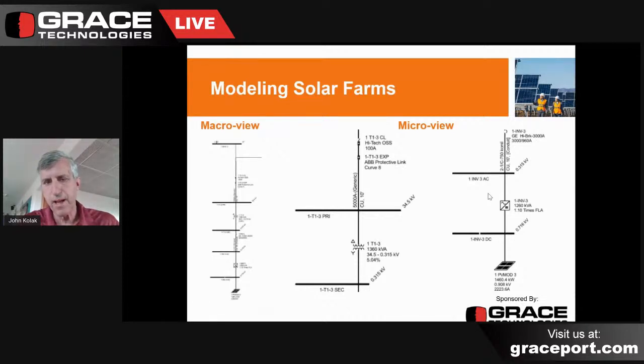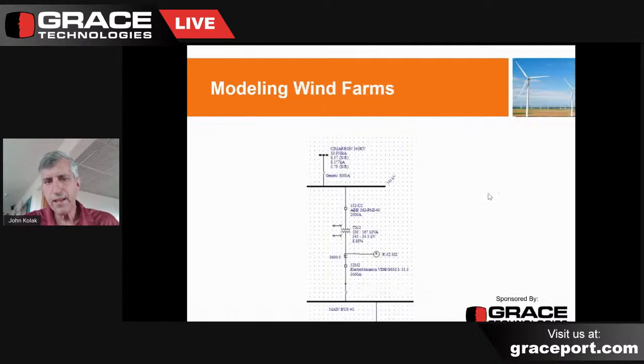Now, if we take the same model for a wind farm, and I want to make sure I get done here in a timely way, the substation itself, and this would be true of the solar farms as well, we normally model using differential clearing on both the main transformer, the GSU or generator step-up transformer, and the 34.5 bus is most often protected by differential relays.